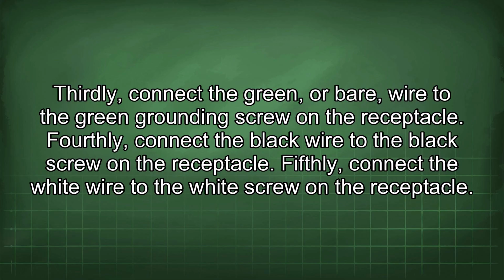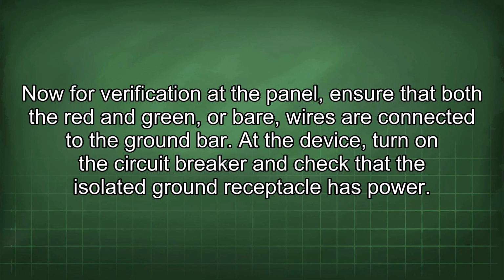Fourthly, connect the black wire to the black screw on the receptacle. Fifthly, connect the white wire to the white screw on the receptacle. Now for verification at the panel, ensure that both the red and green, or bare, wires are connected to the ground bar. At the device, turn on the circuit breaker and check that the isolated ground receptacle has power.